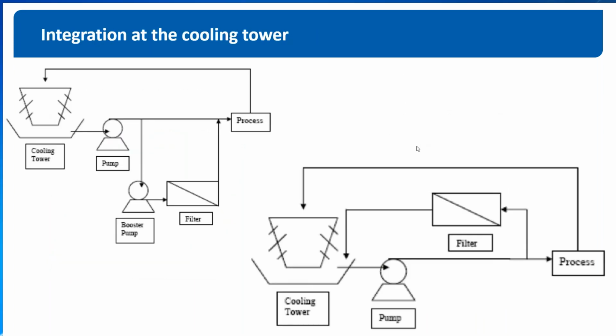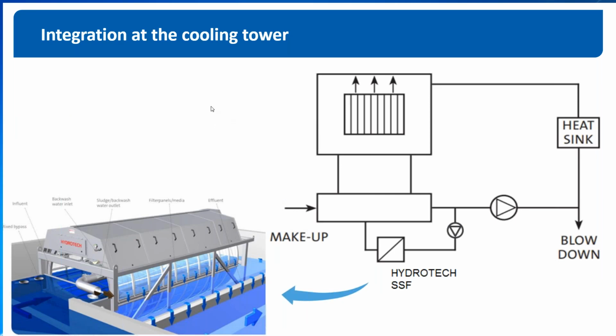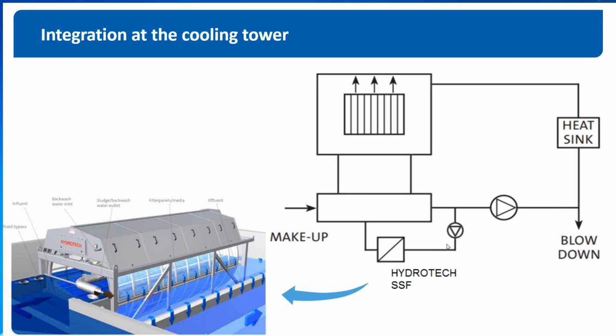So the typical integration at a cooling tower is using a pressurized system. In that case, the filter will be integrated into the cooling tower system either by using a booster pump downstream of the recirculation pump. Otherwise, it could be taking part of the flow, typically about 5%, and bypassing the process, feeding it back to the cooling tower. For the integration of the Hydrotech solution, the recommended mode of integration is to have a separate pump at a similar point to the suction of the recirculation pump, and then passing it through the Hydrotech filter back into the cooling tower basin.